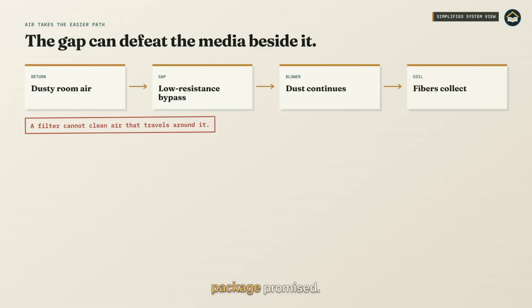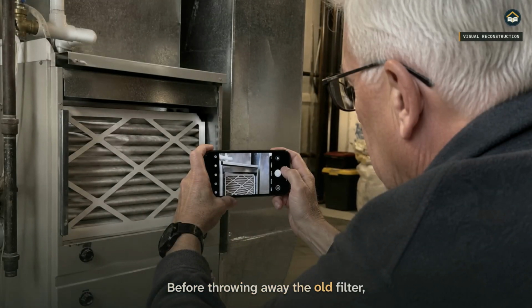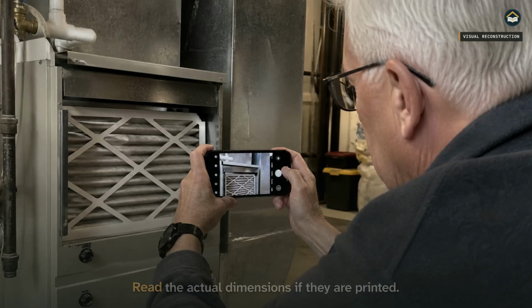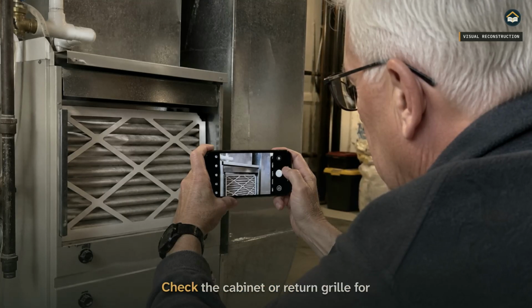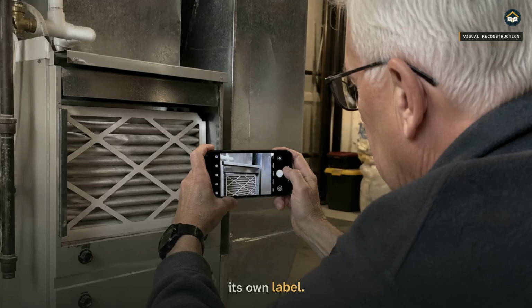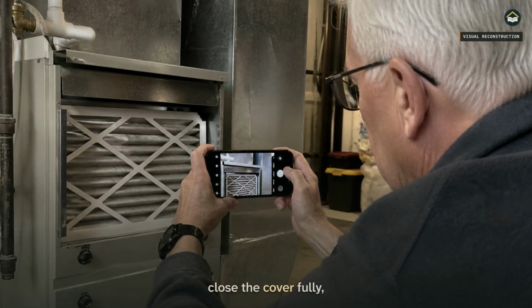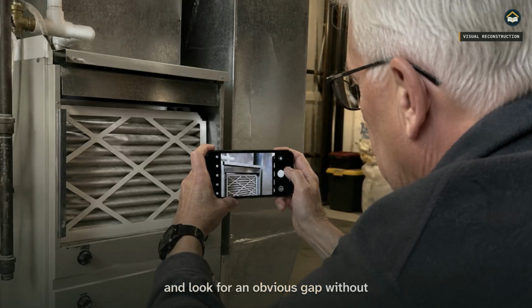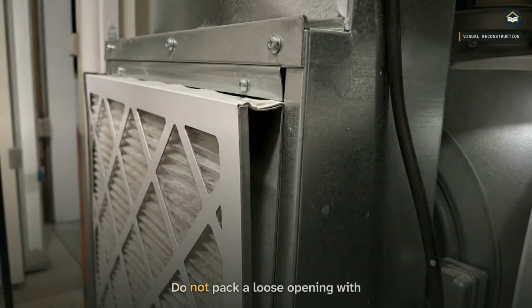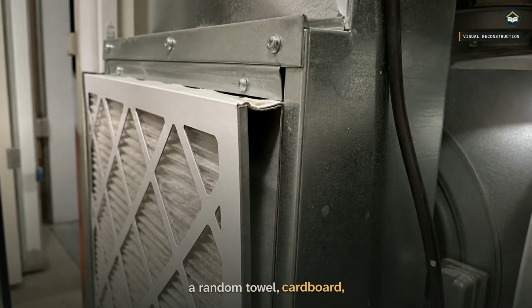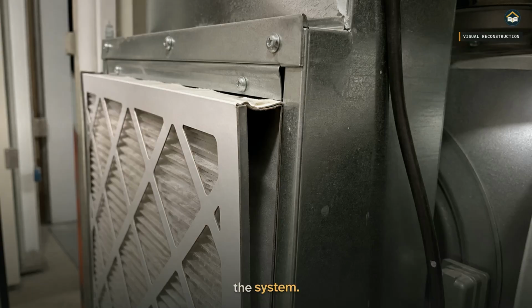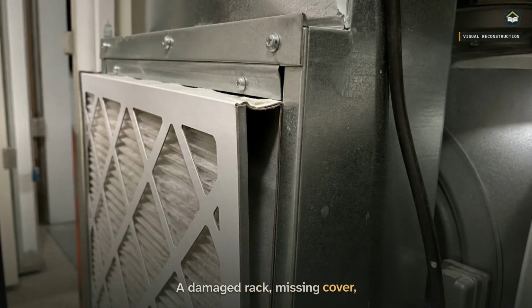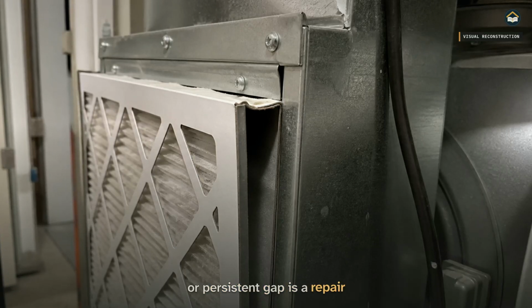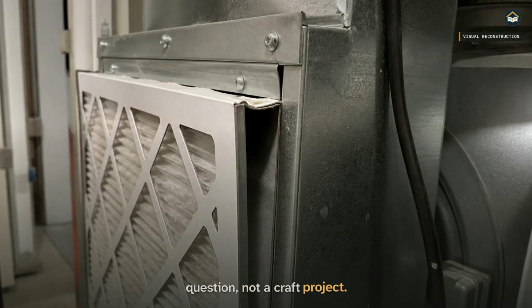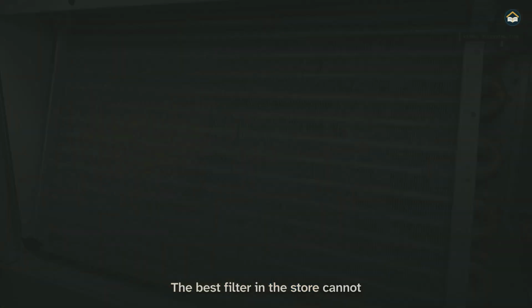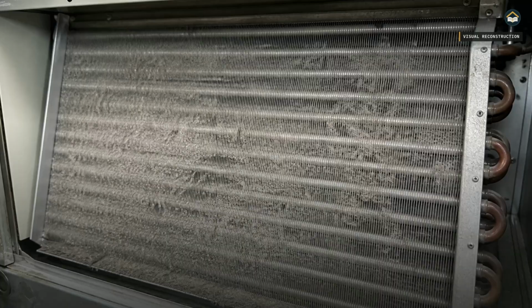Before throwing away the old filter, photograph every label. Read the actual dimensions if they are printed. Check the cabinet or return grille for its own label. Seat the new filters squarely, close the cover fully, and look for an obvious gap without reaching into operating equipment. Do not pack a loose opening with a random towel, cardboard, or tape that can be pulled into the system. A damaged rack, missing cover, or persistent gap is a repair question, not a craft project. The best filter in the store cannot filter air that never passes through it.